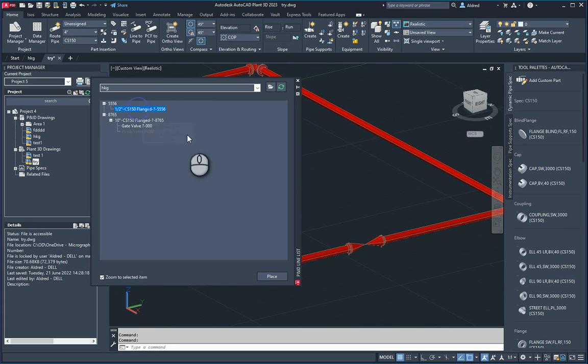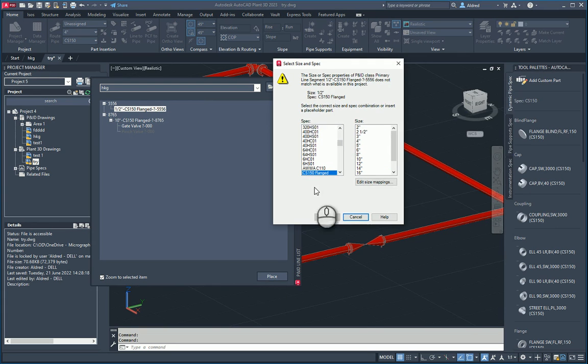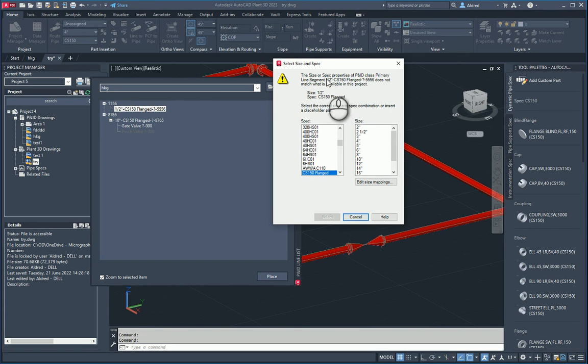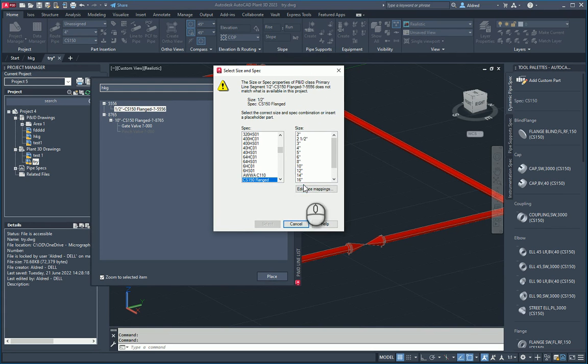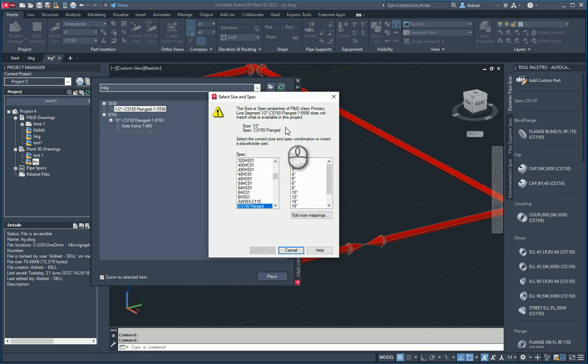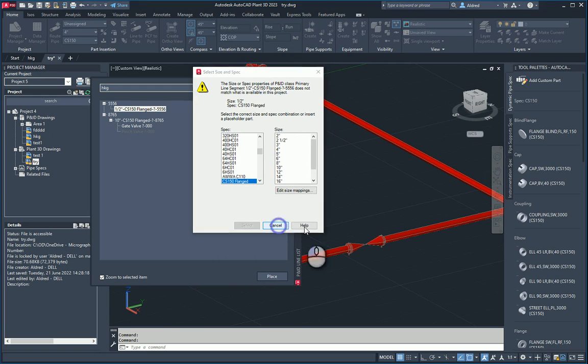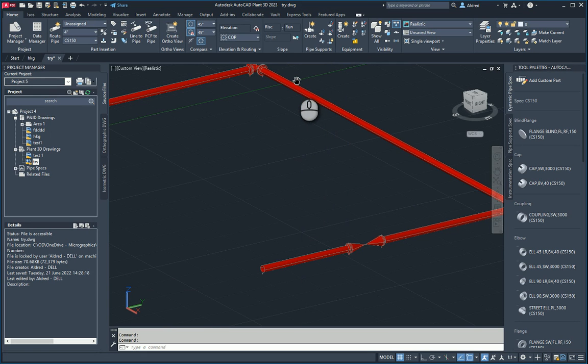Let's go to the out-of-spec pipeline and place it. Immediately it gives me an error: 'The size and spec properties of the class primary line segment does not match what is available in this project.' So it does not match what is available in this spec. I do have that half-inch pipe available in the catalog, but unfortunately that's not what we have in this case. This is a nice way to control that what the guys in the P&ID are doing is also what the guys in the Plant environment are doing — just more checks and balances when creating your plant designs.